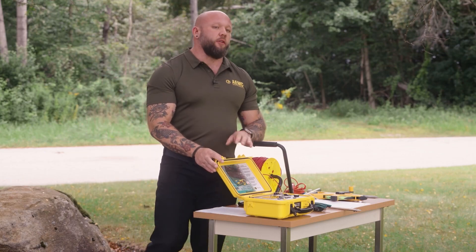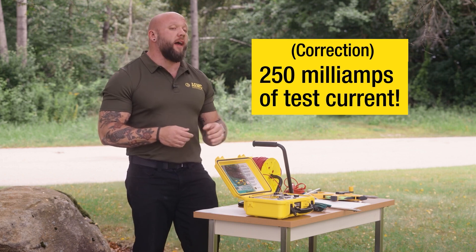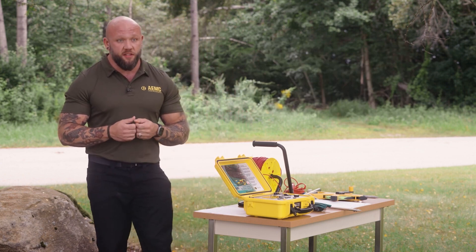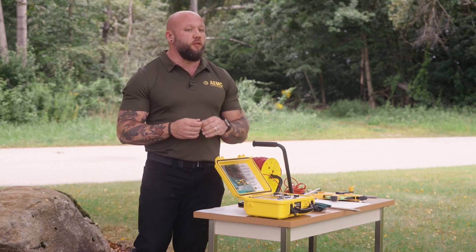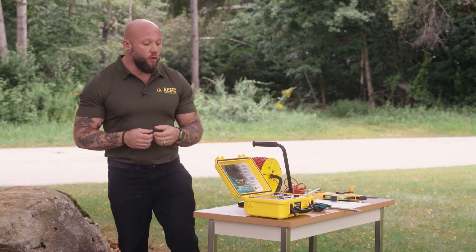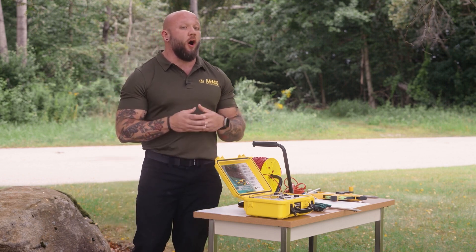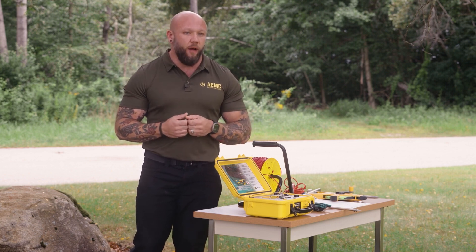The AEMC Model 6472 has up to 60 volts of test voltage, as well as up to 250 milliamps of test current. This instrument is unique in the fact that it has so very many test frequencies as well. Generally speaking, for your everyday testing, you're probably just going to be using the automatic or auto mode for the frequency, but this allows you to customize your test frequency to fit your needs. If you're working around a noisy environment, having that automatic test frequency and all those test frequency options could be the difference between producing a good measurement and having a bad day out in the field.